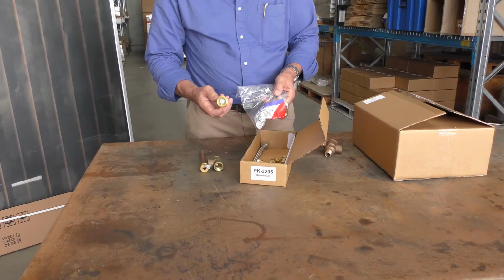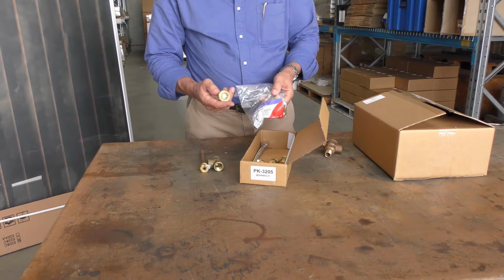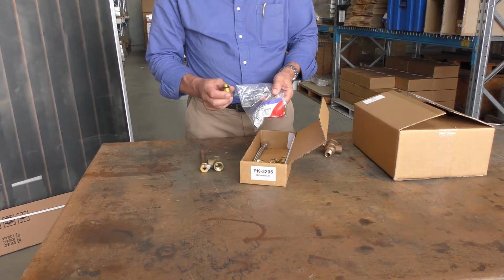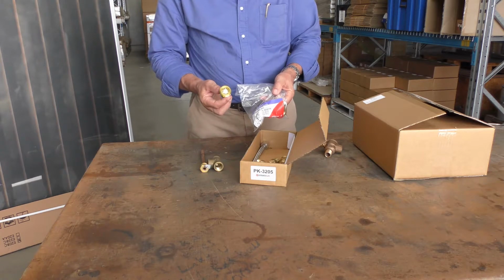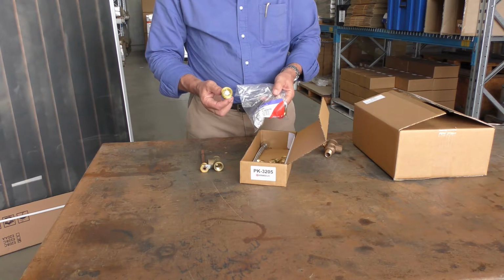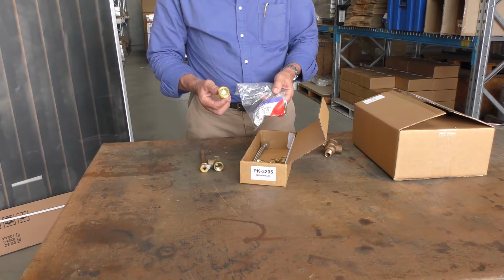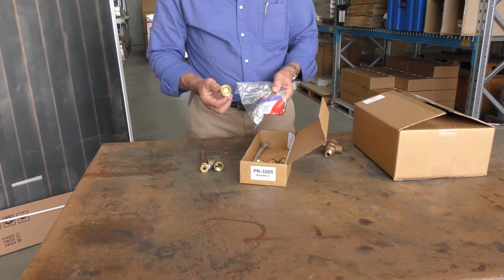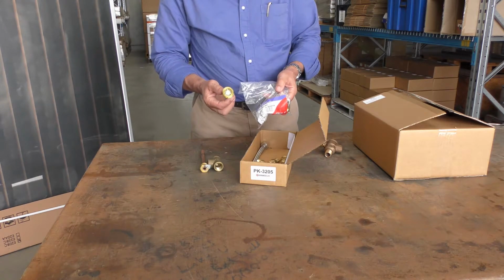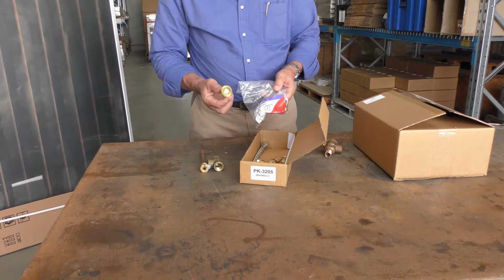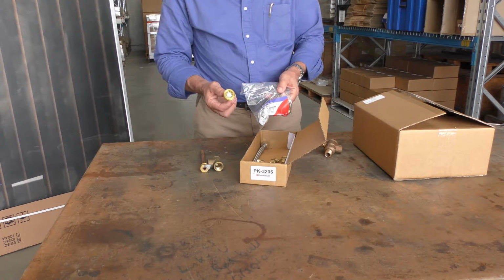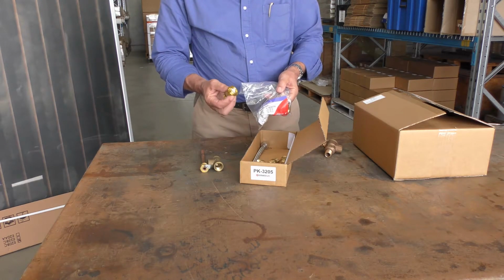This is a connection to the pump - fairly important. This is a non-return valve that we provide. The reason it's there is to stop reverse thermosiphoning at night, which can cause hunting with the pump, because the sensor senses warm water going up and can turn the pump on through a false positive. So this is fairly important to keep as a service item as well.